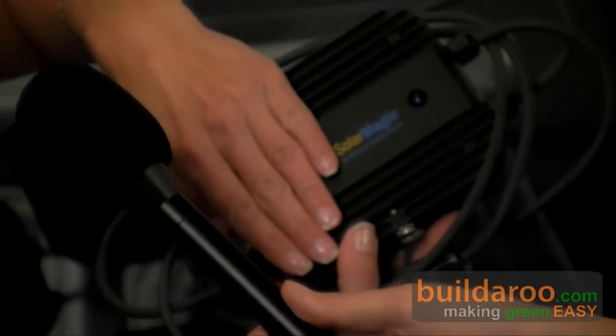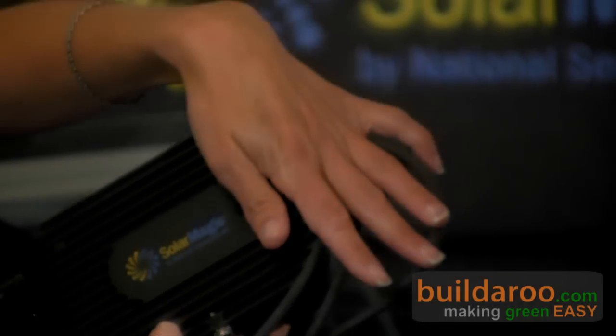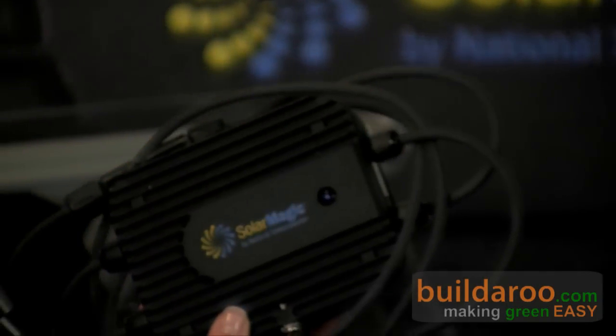At the front end of SolarMagic, we have maximum power point tracking algorithms — we decouple that from the entire system. At the output, we sense the voltage and current environment. The SolarMagic devices installed on every module in a string — but not necessarily on every string — sense their environment. Devices that need to increase current to ensure other modules aren't affected are compensated for, and other SolarMagic devices manage voltage to help the inverter operate at its optimal point. Overall, the SolarMagic devices help at the panel level, at the string level, and with the overall health of the system.